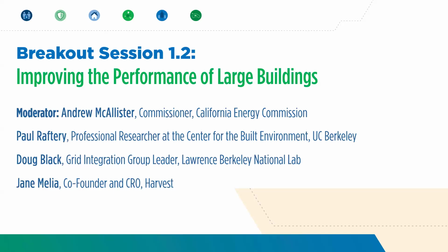The other technology I'd like to flag is reversible air-to-water heat pumps. These are gaining in performance, so more and more are entering the US market. They've been deployed for many years in Europe and other regions, but now they're entering the US market more. They're gaining in efficiency, using lower GWP refrigerants, and performing better at lower temperatures. From my perspective, they're also the engine for thermal energy storage, because they generate hot water which can be the storage medium, allowing cost-effective expansion of heating, hot water storage, and cooling with one single device.